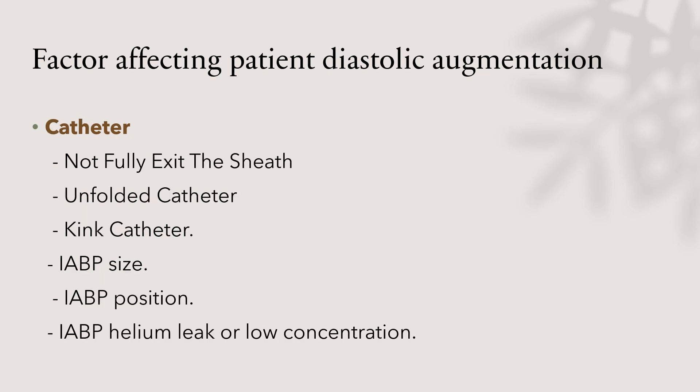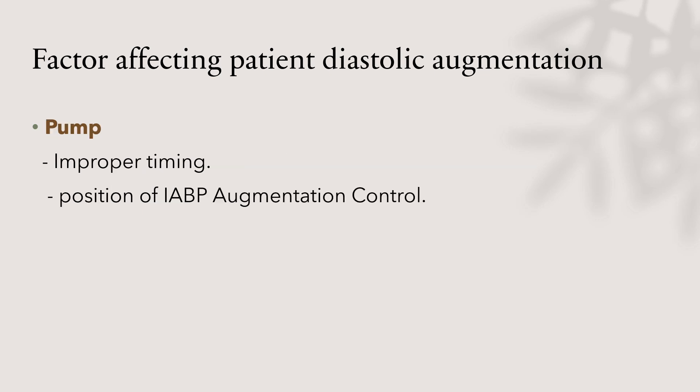Catheter factors include not fully exiting the sheath, unfolded catheter, kinked catheter, the intra-aortic balloon size being very small for the patient, improper position, presence of a helium leak or low concentration of helium inside the cylinder. Pump means improper timing or the augmentation control is not proper for the patient.